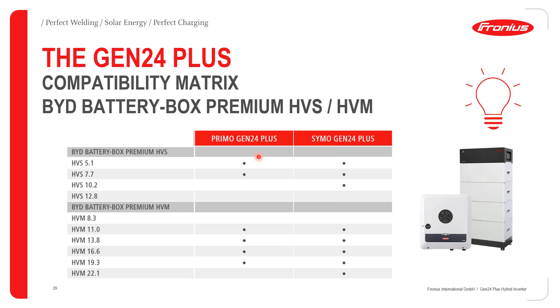As far as the battery compatibility is concerned, the Gen24 Plus inverters are currently only compatible with BYD batteries. So we have what we refer to as the HVS and the HVM batteries from BYD. And then you can see for each series of the HVM or HVS, which of those are compatible with either the Primo Gen24 Plus or the Symo Gen24 Plus. So it's very important that when you design a system for Gen24 with BYD, you check this compatibility matrix to make sure that you have selected the right battery for the right Gen24 Plus inverter.